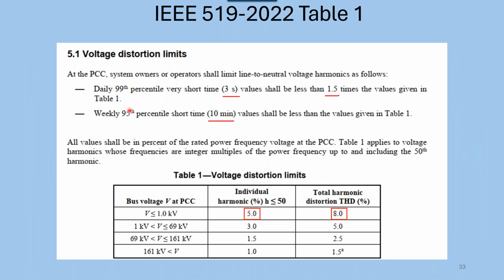And for voltage, we're looking at two things. There's a weekly 95th percentile, and I'll show you this in the report. I've got it in here. That's based on 10-minute values, okay? So they have to be less than the value given in table 1. And then there's a daily, which is a short time, a 3-second rating, which has to be less than 1.5 times the value given in table 1.